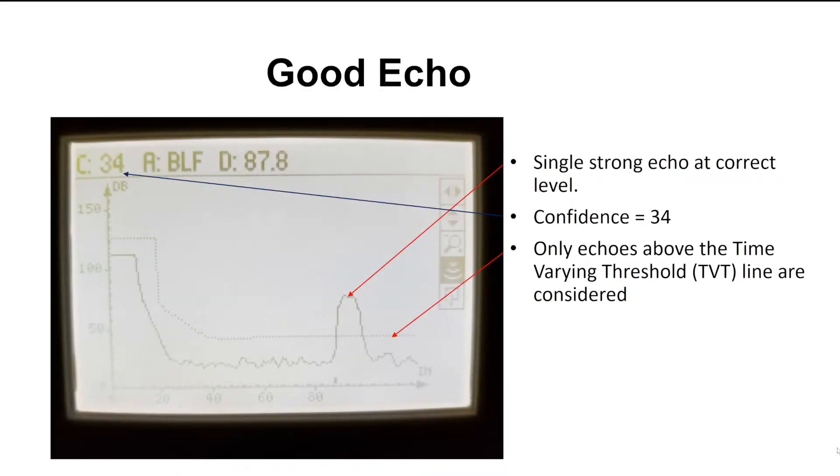In the first example here, I want to show an example of a good echo profile. First of all, what are we looking at? Well, in the upper left-hand corner, we show the confidence shown by C equals 34. Anything above 10 is acceptable, 25 is a really good number, and in this case, 34 is excellent.